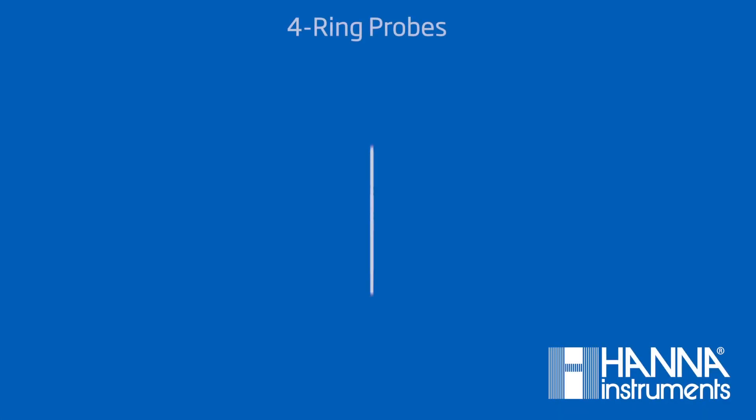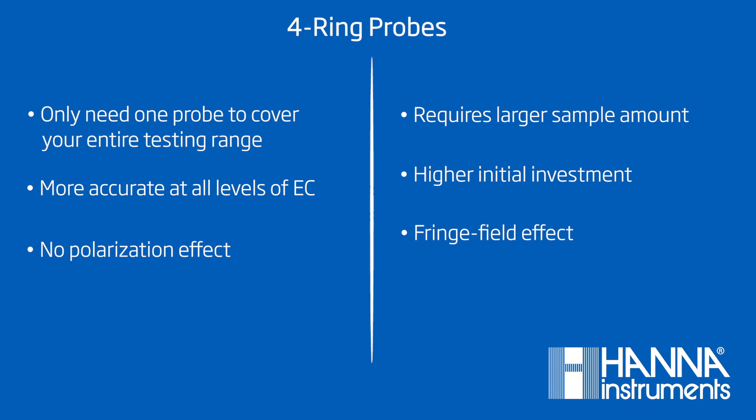When using a four-ring probe, you only need one probe to cover your entire testing range, up to one siemen per centimeter. You also do not have to worry about the polarization effect. The construction of this probe, with how the rings are situated, causes a constant field of current to be maintained around the rings. It acts as a shield.